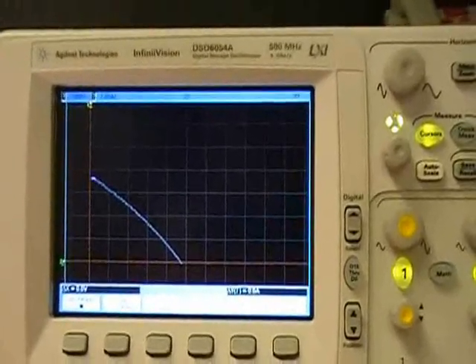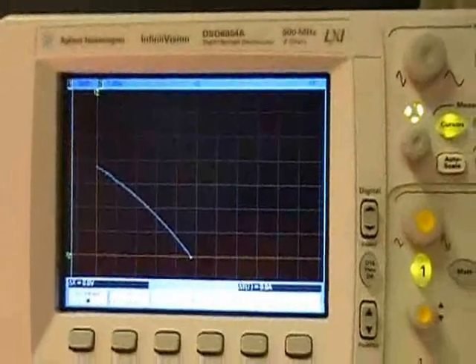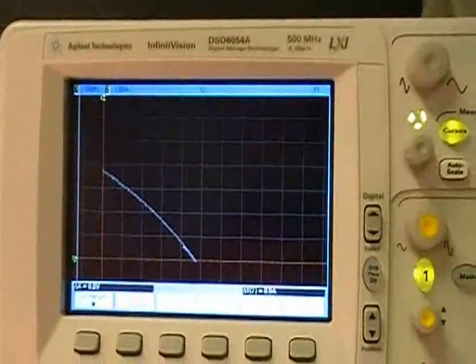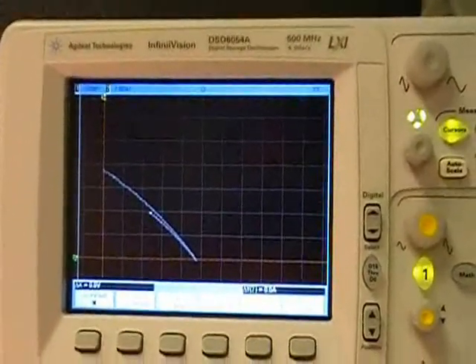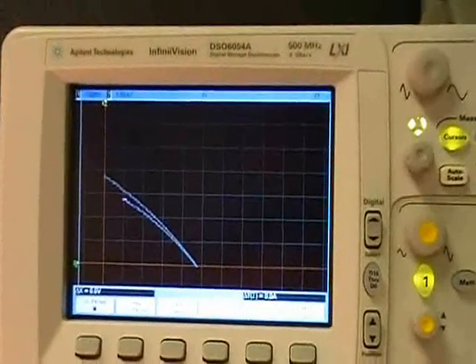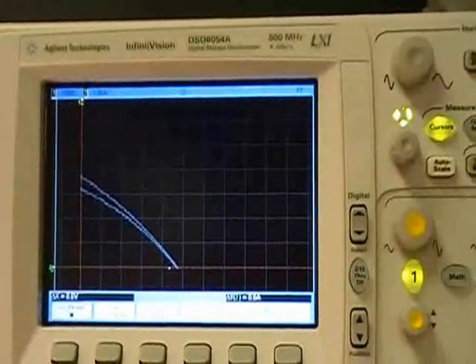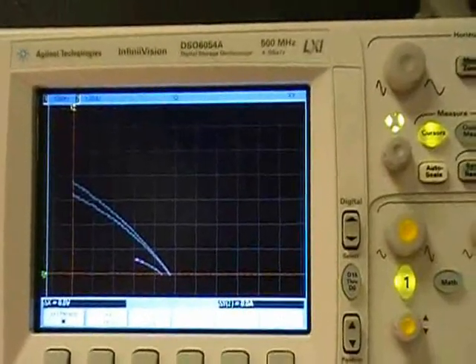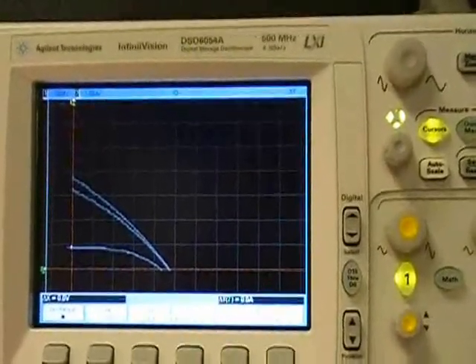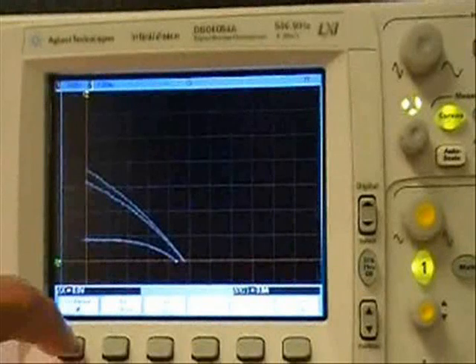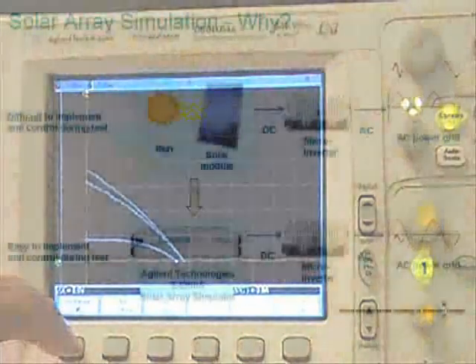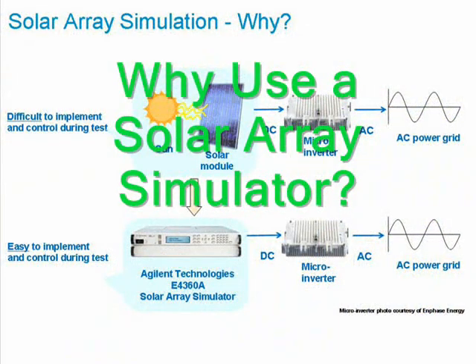We just looked at how a solar cell behaves under full light conditions and two filtered light conditions simulating cloud cover on a solar panel. Each light condition produces a different IV curve, and since a solar panel is normally connected to the input of a microinverter, the microinverter must work with all of these various IV curves on its input. Since the microinverter has to be tested with a variety of IV curves, that's where the solar array simulator is useful — it is expected to mimic the output of a solar panel under various light conditions.